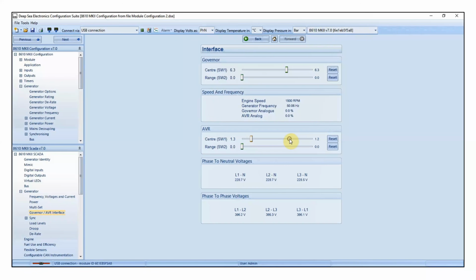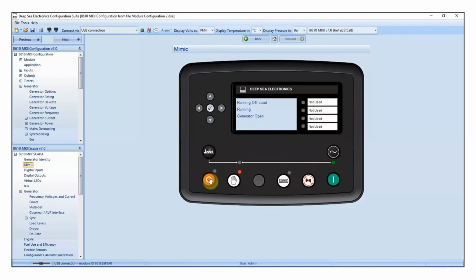Once we've got the switch 1 of the governor correct, we then start adjusting switch 1 of the AVR. In this example, the nominal voltage is going to be 240 volts phase to neutral, or 415 phase to phase. So we adjust the switch 1 of the governor first to get nominal frequency, then we adjust the switch 1 of the AVR to get nominal voltage. And in this case, you'll see as I increase switch 1 of the AVR, the voltage is actually going up. So different to how the governor works. So now you can see I've reached nominal voltage and nominal frequency by adjusting the switch 1 value. And all I do now is stop the generator. And that's actually how you set switch 1.